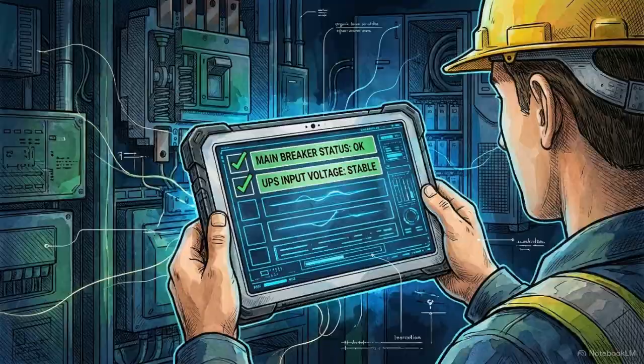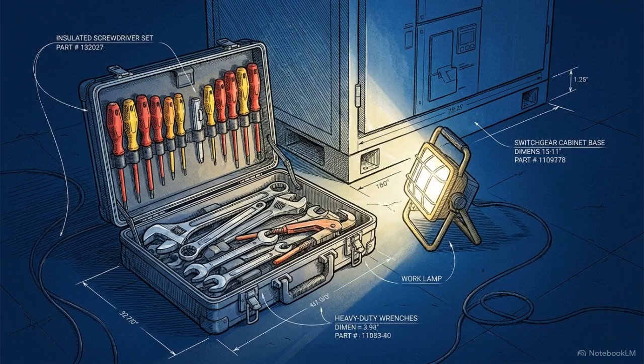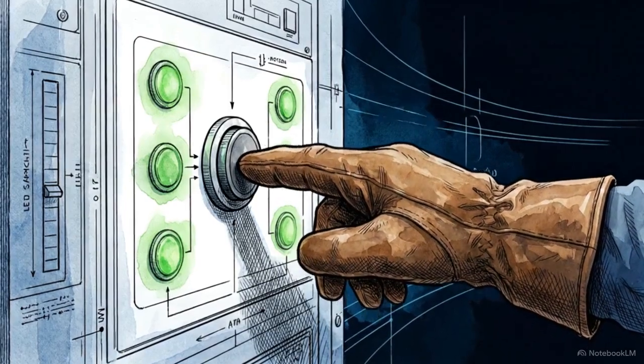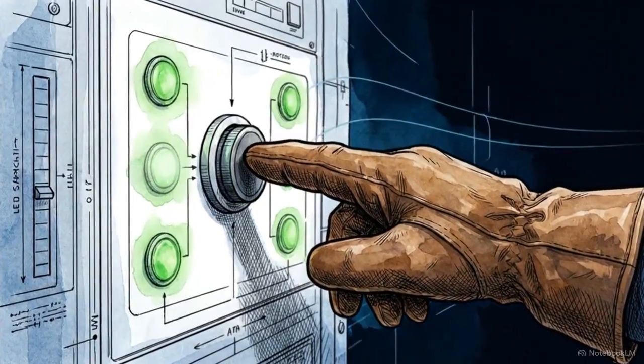You must execute a mandatory diagnostic workflow: read the alarm, record the system state, and physically inspect the switchgear to identify the blown fuse, control wiring fault, or jammed mechanism. You correct the root cause first. The reset button is purely an administrative tool. It is only pressed to clear the controller's logic board after the physical world has been proven safe.